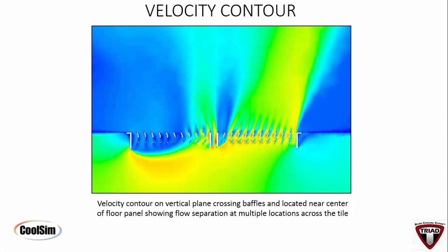Well, I'm not spending my money on it. So what you've got is a couple problems here. One, this leading edge again is causing all kinds of problems. So these fins that are here never get to see the air. There's nothing there for them to do. The air is not moving up.